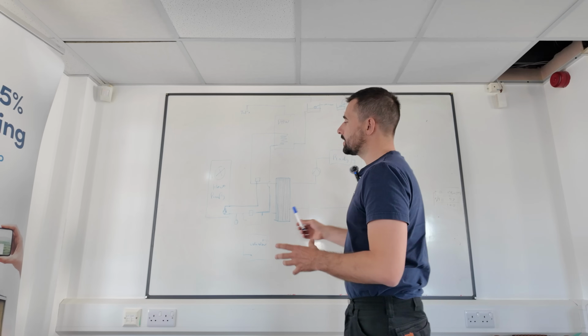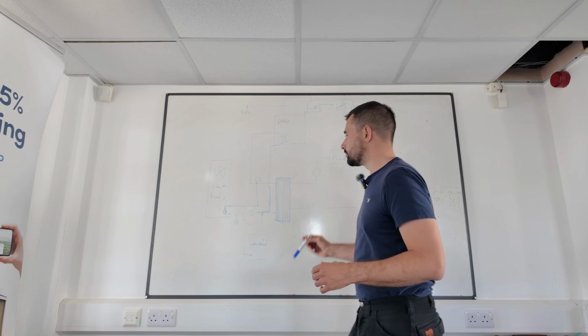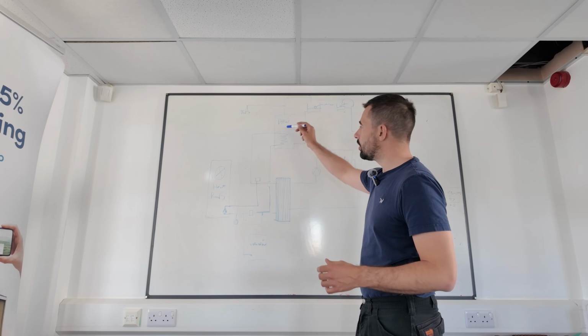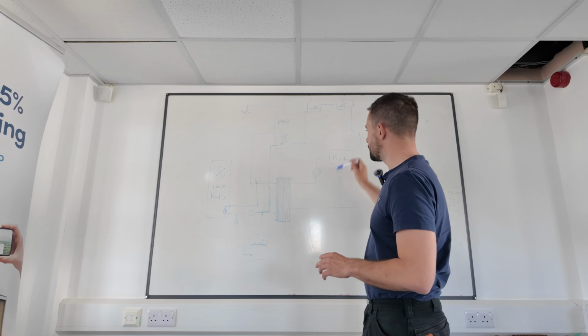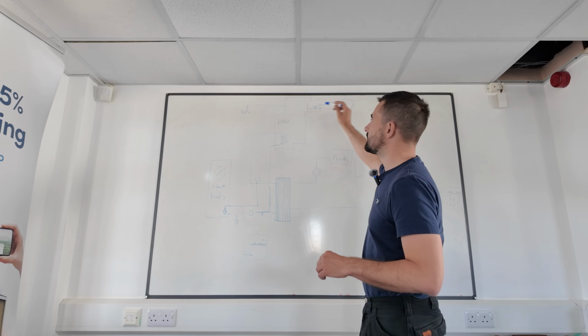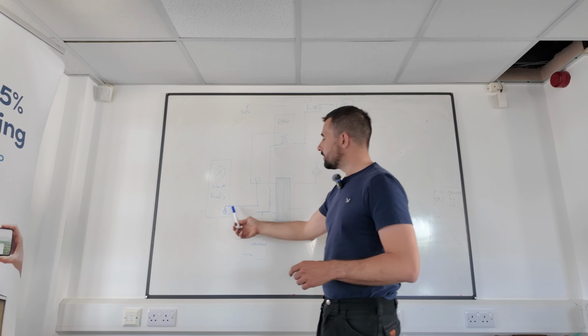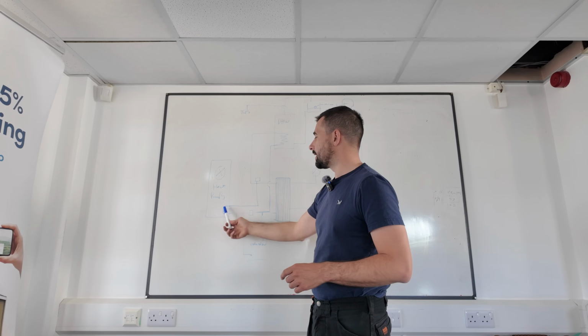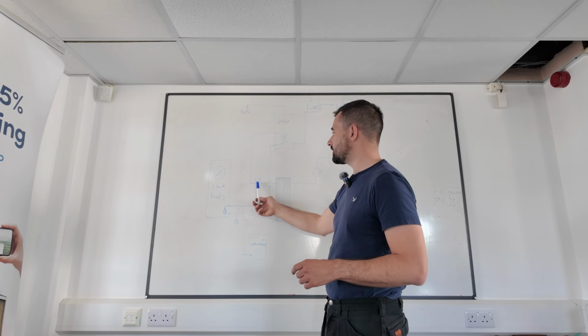So essentially we've got the heat pump unit, we've got the heat exchanger here, hot water tank, volumizer, radiator circuit, and then the header tanks in the loft. So if you imagine we've got the heat pump with its pump in, it'll drive the water through to the diverter valve.